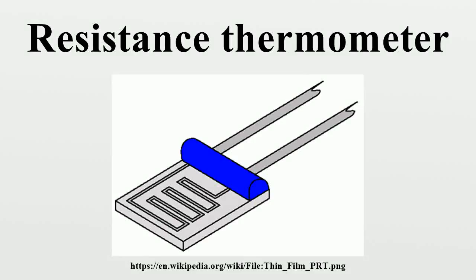Resistance thermometers, also called resistance temperature detectors, are sensors used to measure temperature by correlating the resistance of the RTD element with temperature. Most RTD elements consist of a length of fine coiled wire wrapped around a ceramic or glass core. The element is usually quite fragile, so it is often placed inside a sheathed probe to protect it. The RTD element is made from a pure material, typically platinum, nickel or copper.